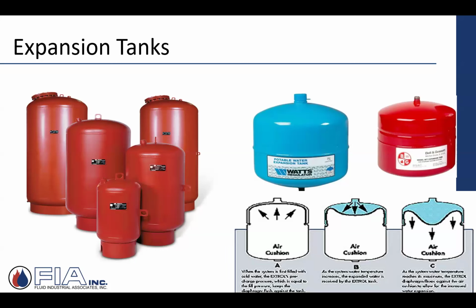What I like about this picture, it's very, very simple. It's almost like a smaller residential tank. But what happens is when these tanks get installed and the system is off, it's not hot, it's cold, you're just putting the system together, there's not supposed to be any water in the tanks, just air. Whereas that old steel compression tank that was hanging up had 55% water. It was a much bigger tank. There was a lot more details. It was very challenging or finicky. These guys are much less finicky, very flexible, very easy to install.